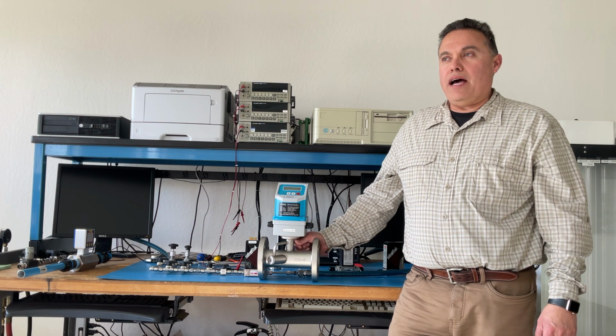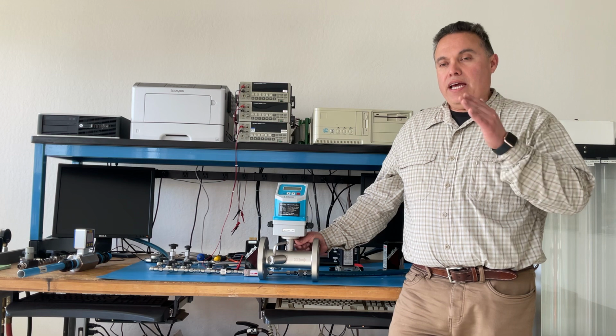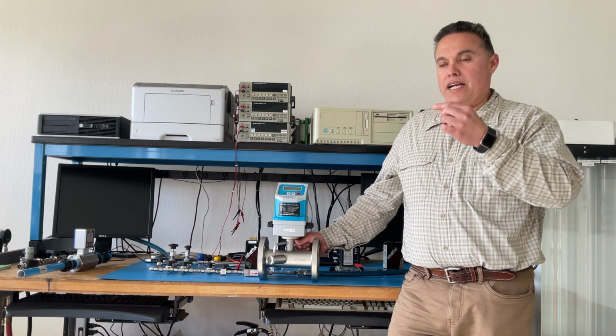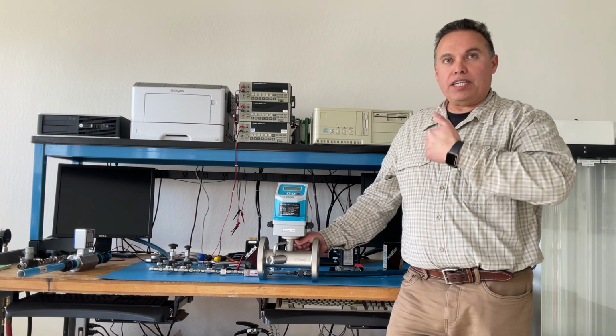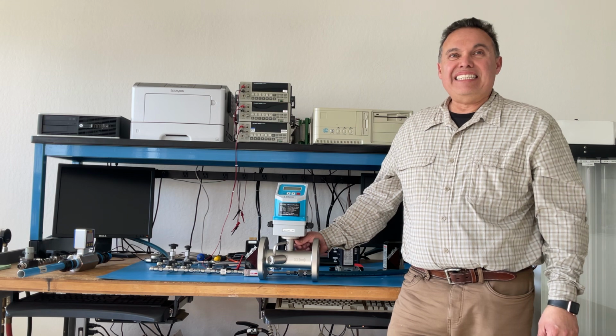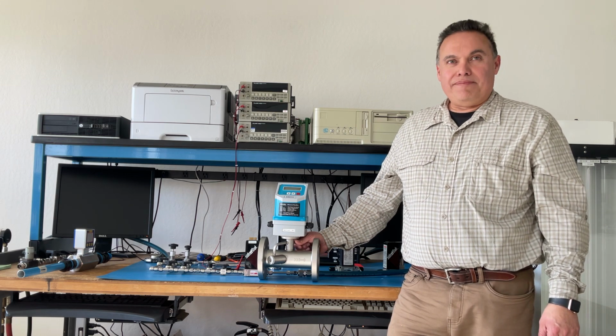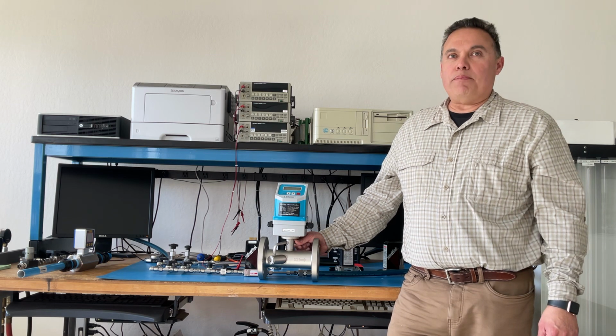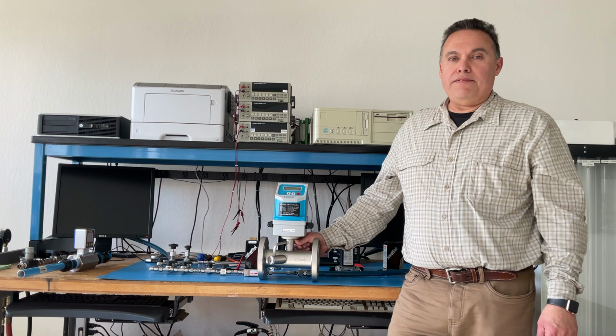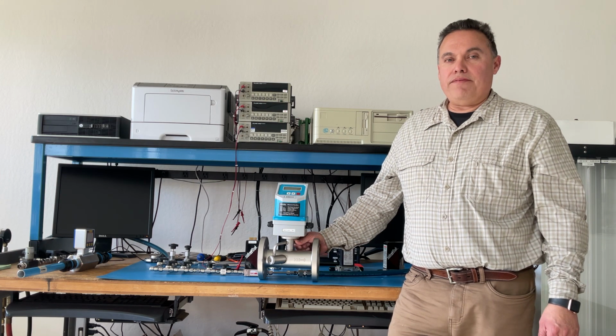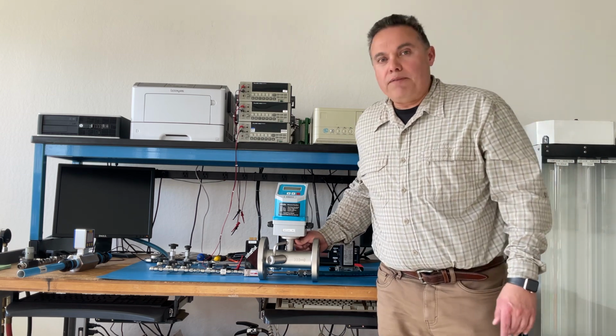and because of the way that the meter works, it measures across the entire flow profile of the pipe. And what I mean by that is that every velocity vector and every molecule that comes to it, it's traversing that twice. It's not like we just have one little spot that's measuring how fast the flow is at that one spot in the pipe. We're measuring the entire pipe. Yeah, so it's more accurate. It's not a point velocity measurement. It's full span of the pipe ID measurement. So it's a very, very accurate measurement because of that. Upstream, downstream doesn't have to be all that great for it to work properly, so you don't need to have a fully developed flow profile for this to work.